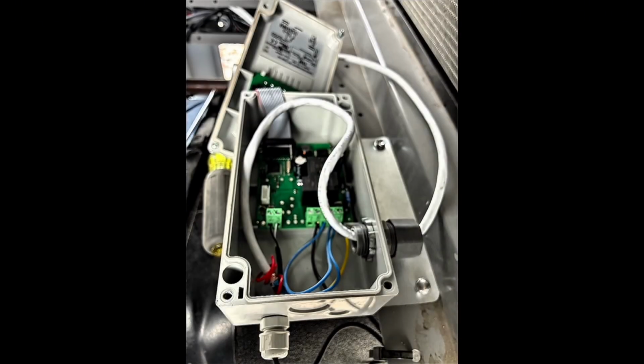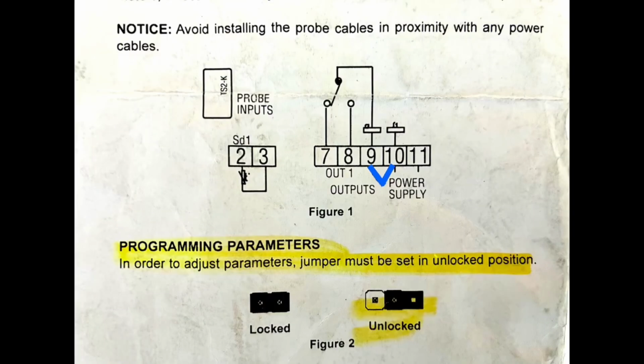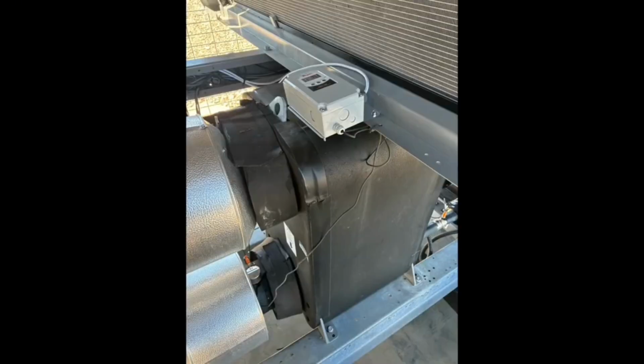So pretty simple. I installed the temp switch to this bracket up at the chiller. Underneath the condenser coils there, you can see there is a rail I mounted it to, and our 24 volt wire comes in. Here's a wiring schematic for that temperature switch. You gotta connect terminal 9 and 10 on this one to send power out back down to energize that relay. As it looks like all finished up.